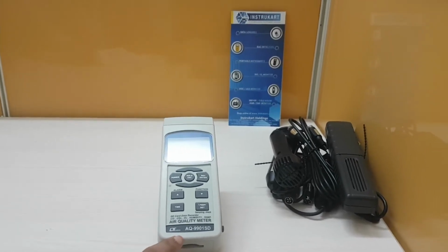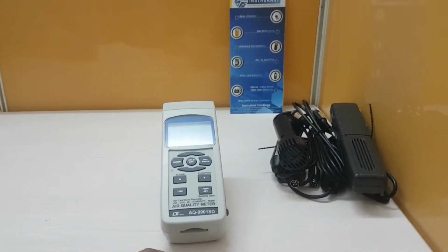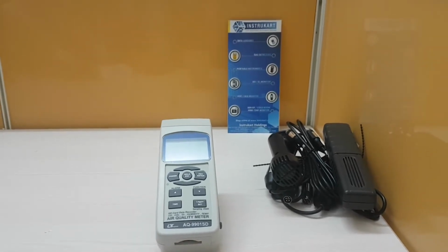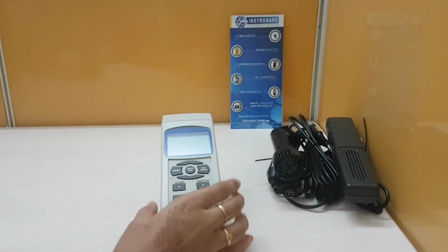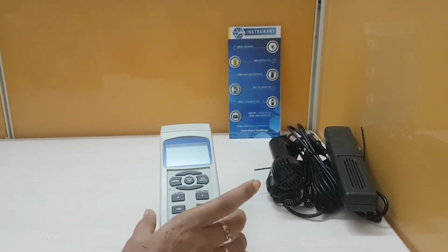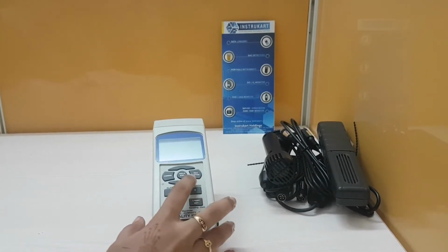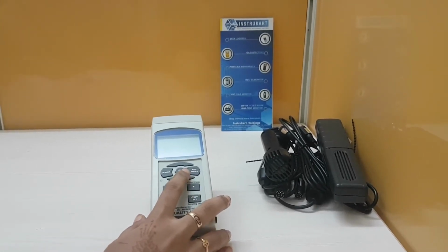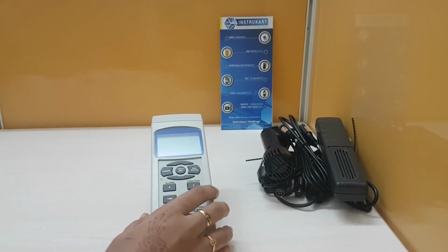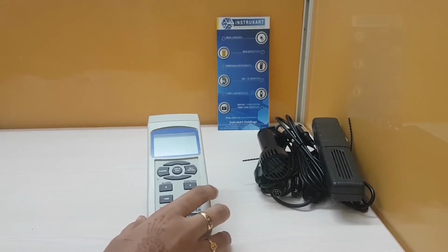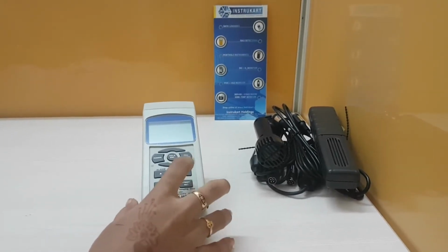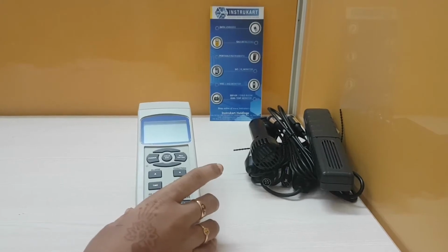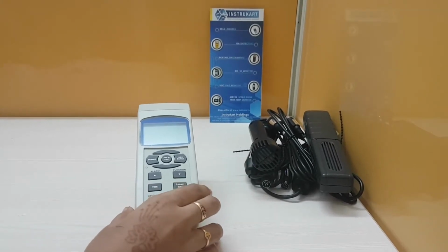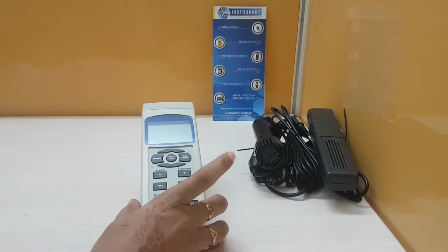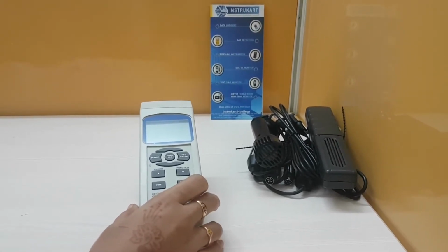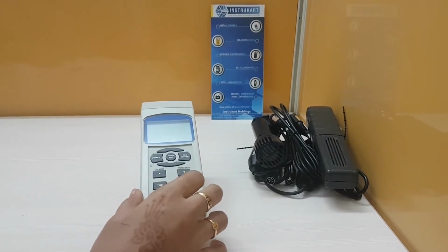We do have advanced settings like SD memory card format, set clock time, set sampling time, auto power off, and set beep sound on or off, decimal point of SD card, temperature unit setting, alarm value setting, etc. And also we have data hold feature with which freezes the display reading. Coming to the memory recall, maximum and minimum values are displayed in memory recall. Coming to the sampling time of display, it is approximately 1 second, and data output can be through RS-232 or USB PC computer interface. Coming to the power supply, it has alkaline or heavy duty DC 1.5 volts batteries with 6 pieces.